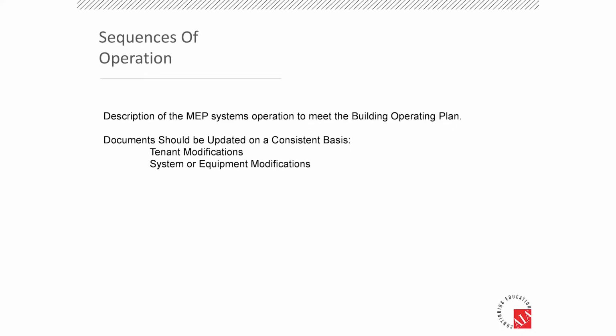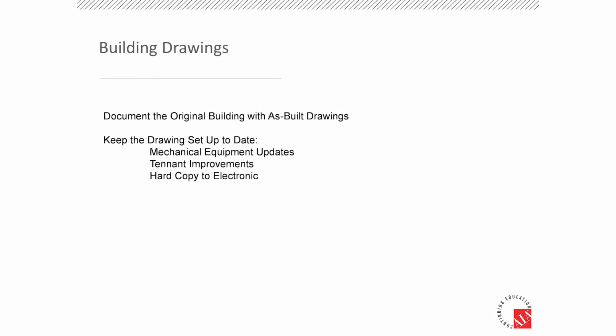Final item in these three kind of written documents is your sequence of operation. So this is describing those systems in the systems narrative, how they operate to meet your building operating plan. This starts with the as-built drawings from when your systems are installed, and it should be modified on a regular basis to include updates to the mechanical equipment, changes to your sequence of operation, and then if you have tenant modifications to the systems as well. So if you have tenant improvements and they add it or build it out, that should be included. Now, the sequence of operation can be a challenging document to keep updated because generally it's easy to modify the sequence of operation without going back to that source file or source documentation to update that.